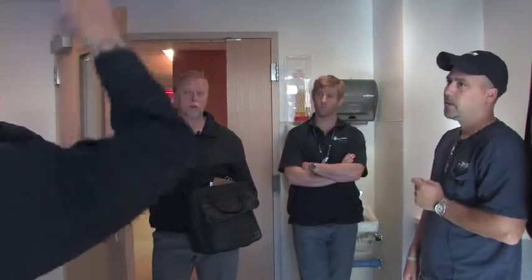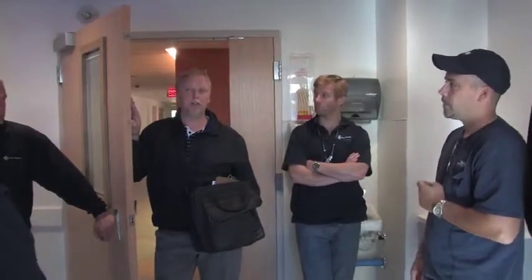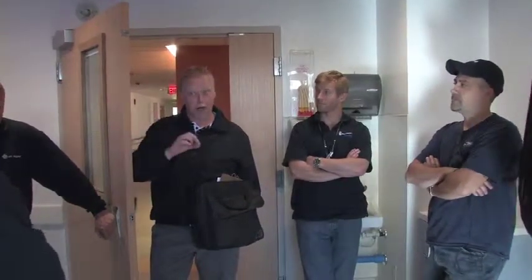The transformer could be good. If you have a controller that's bad, something that's shorted out, it's going to blow that fuse before it blows the transformer. Is it an individual inline fuse for each controller, or just one for the main transformer? Main transformer. So if you short something accidentally, you could potentially take down a bunch of stuff, multiple boxes instead of a single box. Normally it's a transformer per box, but because of the fire ratings issue, because it's on critical power, yeah.